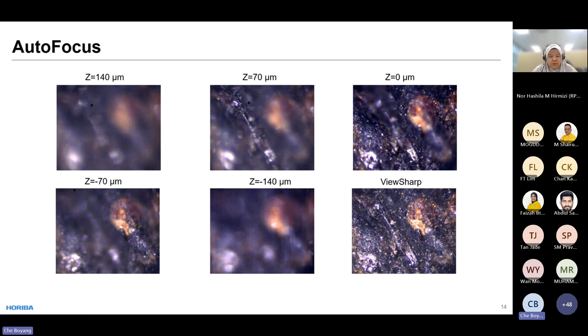So now on Horiba, we provide the so-called ViewSharp function, which deals with this kind of non-flat sample. By using ViewSharp, you will be able to adjust the focus on each pixel. So even for a non-flat sample, you will be able to get a very good image like this, so that every pixel is in good focus. And moreover, because it already records the different heights of your sample, you will finally get this kind of 3D image so that you know the topography of your sample surface.